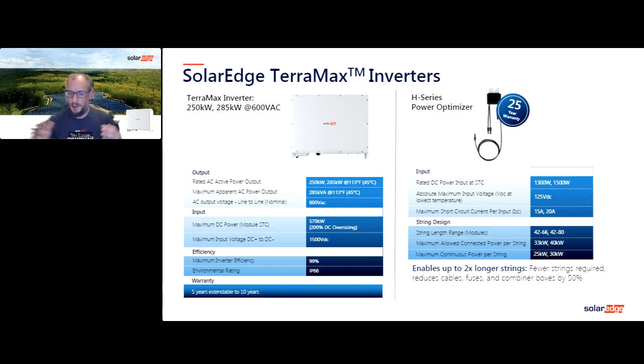And then they allow for a very wide amount of modules to be connected to 1 string. So that's really one of the key benefits that SolarEdge brings when we pair this optimizer with our inverters: we allow for string stretching and having mismatch of strings, and really being able to offer a lot of flexibility when it comes to designing a solar plant from the beginning. A lot of times we see people trying to design plants after the fact using what you would normally string a string inverter to. But when you use our H series power optimizers with the TerraMax, it really allows you to expand your frame and allow you to design for the site rather than designing to your inverter that you chose. So it provides a lot of flexibility.